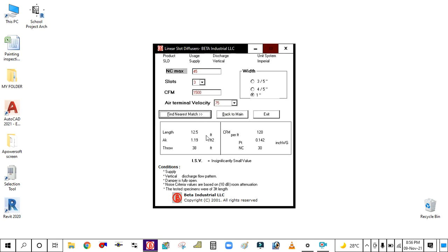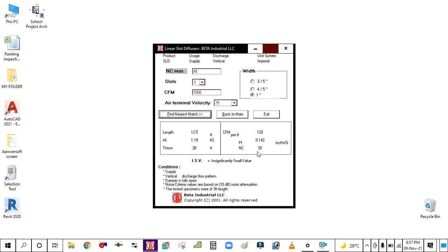You are getting 12.5 feet as the length of the slot diffuser, CFM is 120, critical area is 1.19 square feet, throw is 38 feet, and total pressure is 0.142 inches of water gauge. Noise criteria is 30.